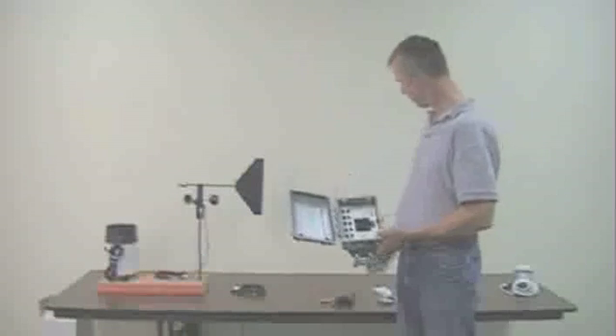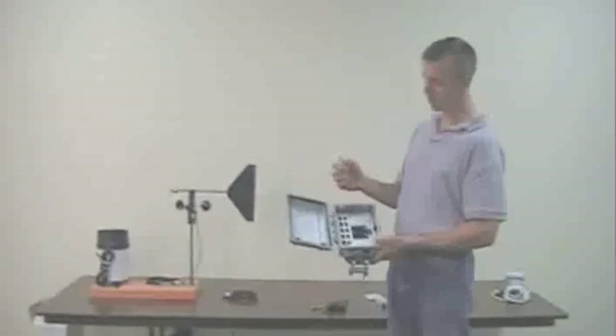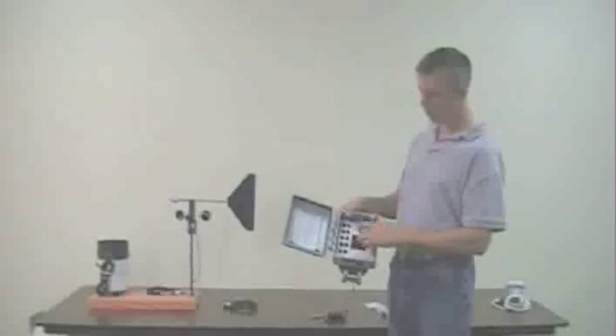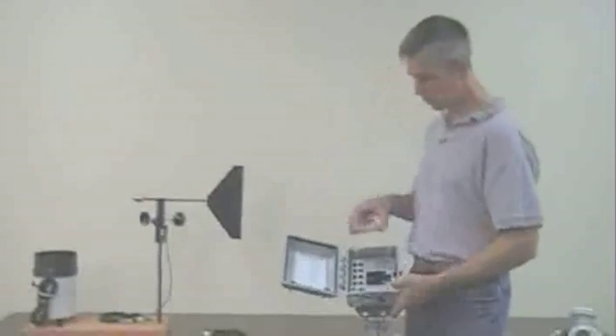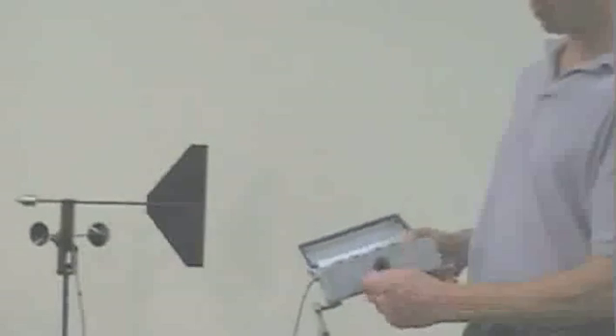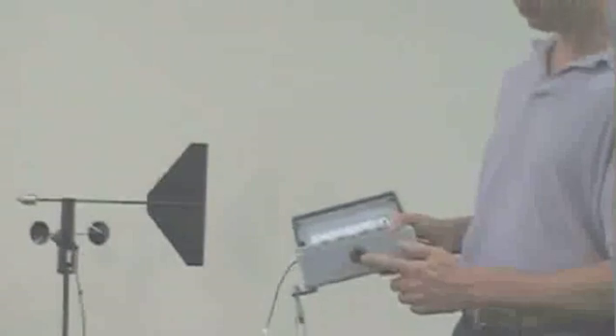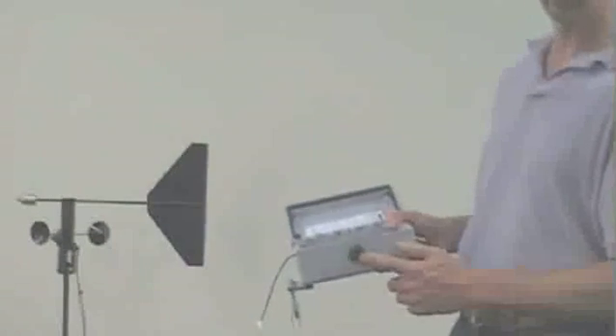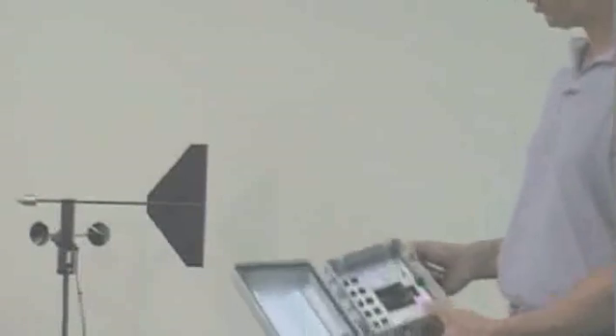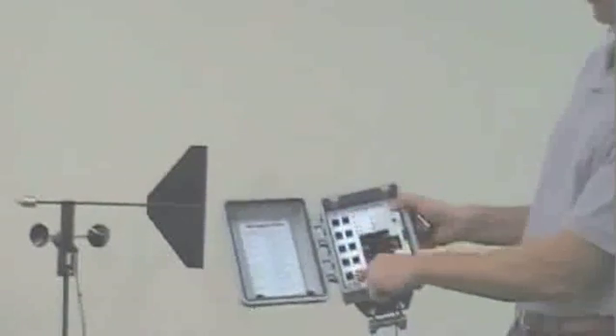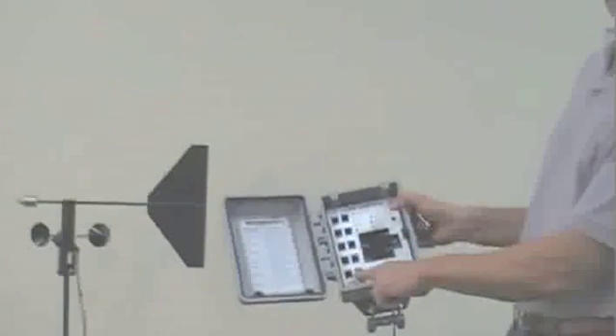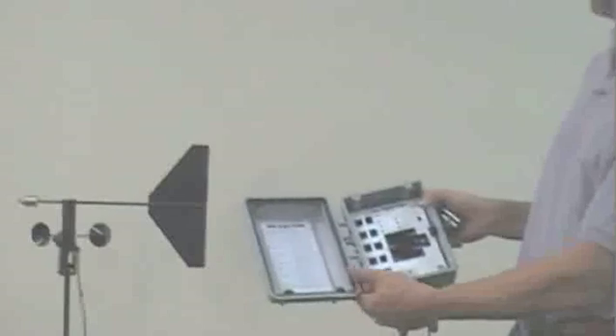You can see these are the batteries that come with the unit. They get installed into here, go underneath this cover plate. This is the actual communication port that you would hook up to your computer to actually talk to the logger. And then here are the actual ports for the sensors. That's what we'll be plugging all of those into.